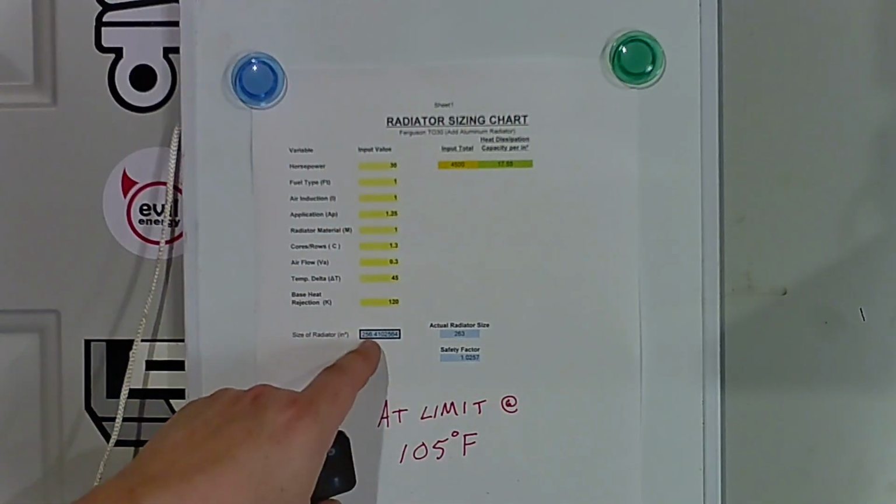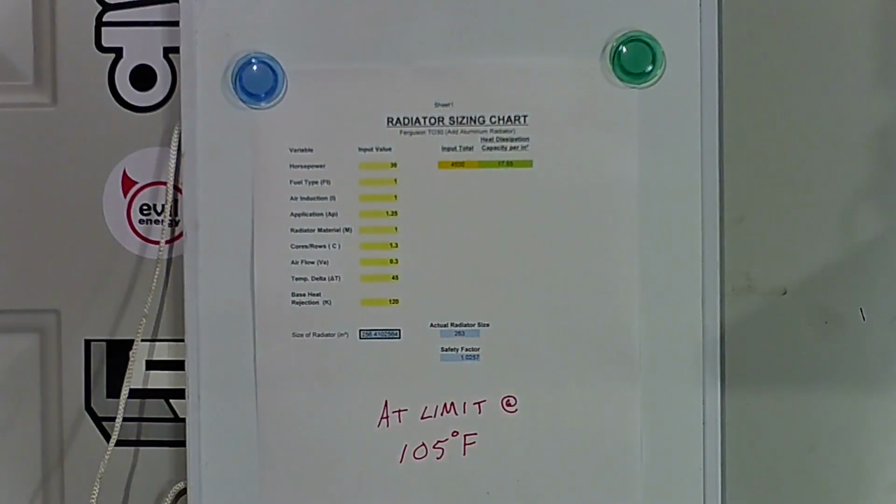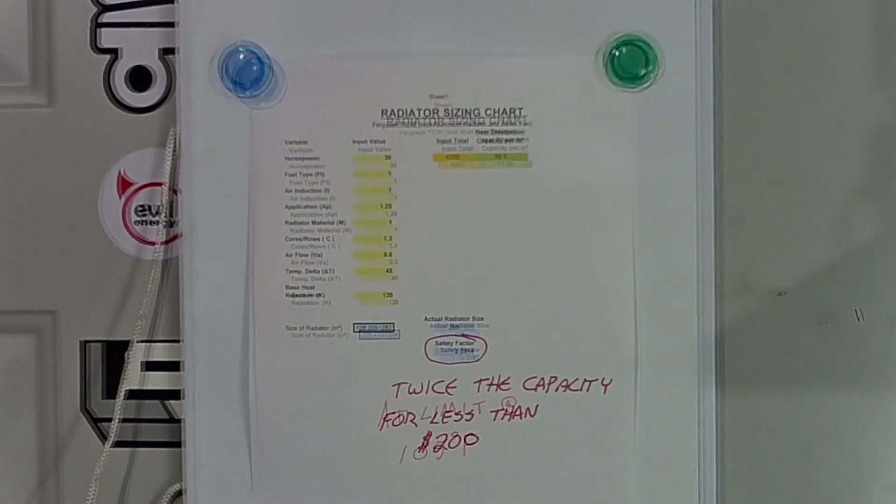That's going to give me a required radiator size of 256 against a 263 actual radiator size. So that will work, but I'm at my limit at 105 degrees.